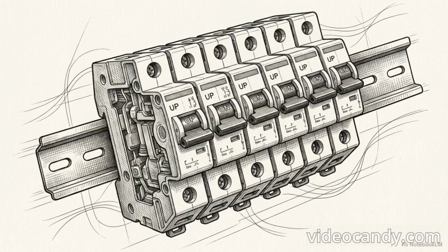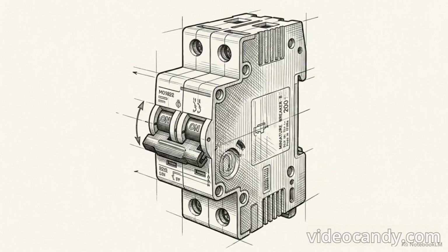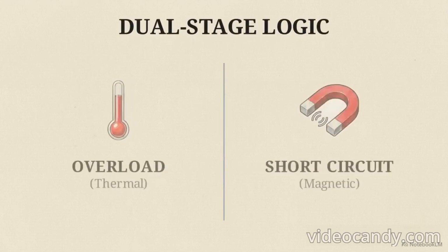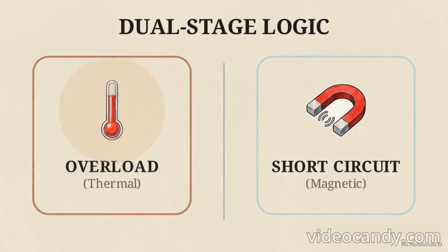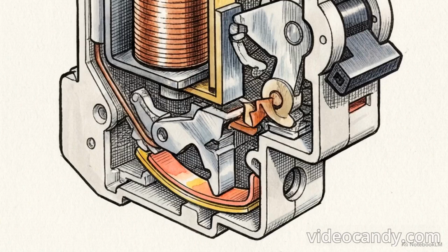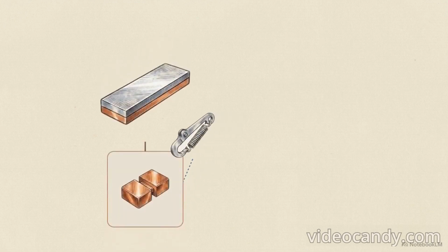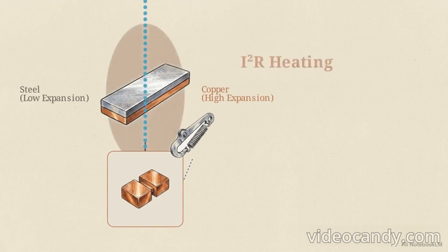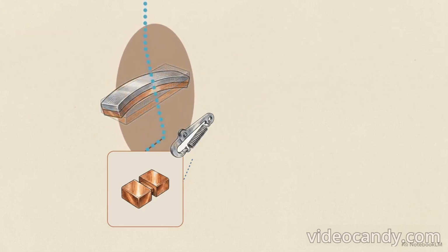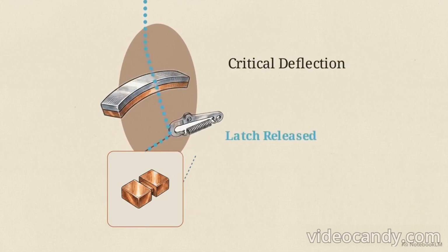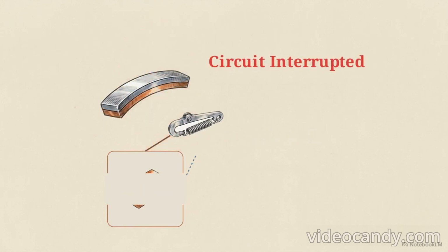We needed a device that could mimic the physical interruption of a fuse, but do so with non-destructive, resettable mechanics. The miniature circuit breaker, or MCB, solves the replacement problem by operating as an automatic mechanical switch. Rather than destroying itself, it uses dual-stage logic to map internal hardware to specific fault profiles. Stage 1 is thermal operation, designed to catch the exact same progressive cable overloads that would melt a fuse. Inside the MCB, the current passes through a calibrated bimetallic strip, two joined metals with completely different expansion coefficients. As excess current causes continuous I²R heating, the two metals expand at uneven rates, forcing the entire strip to physically bend. Once the deflection hits a critical physical angle, it releases a mechanical latch that forces the main contacts open.